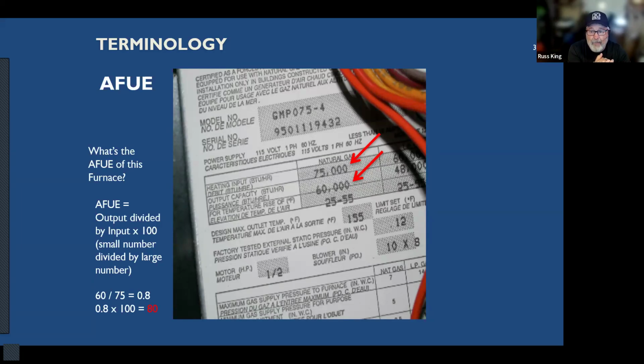And these are all the old naturally aspirated furnaces, and it was all going up the flue. Those B vents that come off the furnace get really hot, and if wood's touching them, they can actually catch on fire if you're not careful. All that heat would go up through the roof and outside the house, and some of it would come inside the house. So they figured out some very clever ways to capture that heat that's going out through the B vent and escaping through the roof, by taking the combustion products and running them back through another heat exchanger and letting the air cool that down.